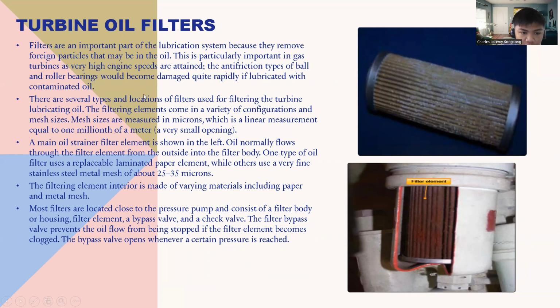These are several types of filter applications used for filtering the turbine lubricating oil. The filtering elements come in a variety of configurations and mesh sizes. Mesh sizes are measured in microns, which is a linear measurement equal to 1 millionth of a meter. A main oil strainer filter element is shown on the left. Oil normally flows through the filter element from the outside into the filter body. One type of oil filter uses a replaceable laminated paper element, while another uses a very fine stainless steel metal mesh of about 25 to 35 microns.